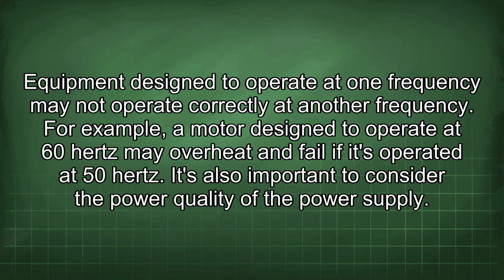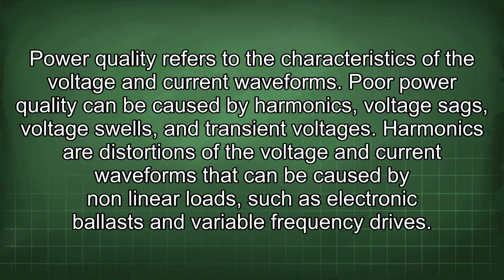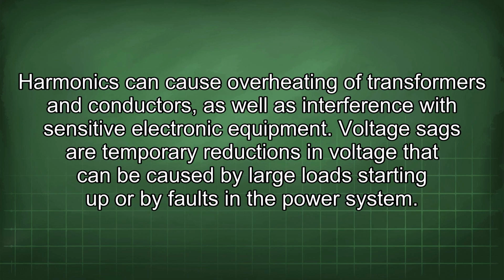It's also important to consider the power quality of the power supply. Power quality refers to the characteristics of the voltage and current waveforms. Poor power quality can be caused by harmonics, voltage sags, voltage swells, and transient voltages. Harmonics are distortions of the voltage and current waveforms that can be caused by nonlinear loads, such as electronic ballasts and variable frequency drives. Harmonics can cause overheating of transformers and conductors, as well as interference with sensitive electronic equipment.